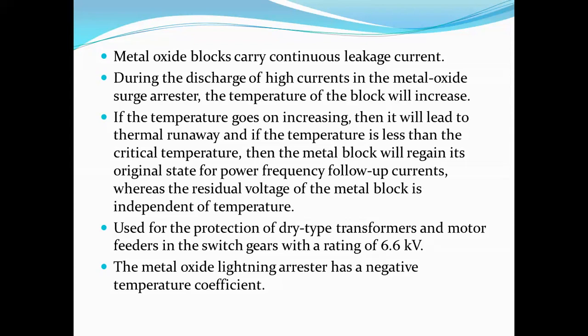At that time the temperature of that block, that arrestor, gets increased, and if the temperature goes on increasing, then it will lead to a thermal runaway. And if the temperature is less than the critical temperature, then the metal block will regain its original state for the power frequency follow-up currents, whereas the residual voltage of the metal block is independent of the temperature.